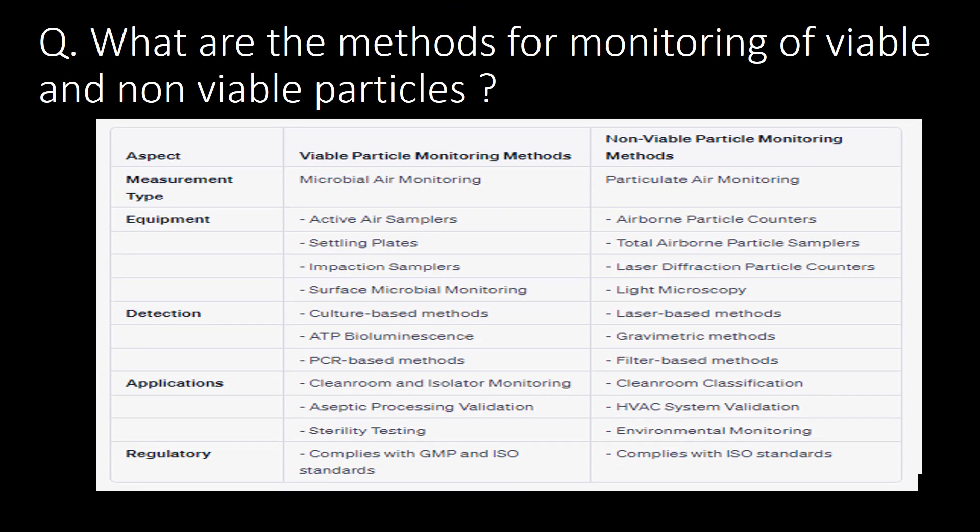What are the methods for monitoring viable and non-viable particles? For viable particle monitoring, we use active air samplers, settling plates, impaction samplers and surface microbial monitoring. For non-viable particle monitoring, we use airborne particle counters, total airborne particle samplers, laser diffraction particle counters and light microscopy. You can refer to the table below for detection, application and regulatory requirements.